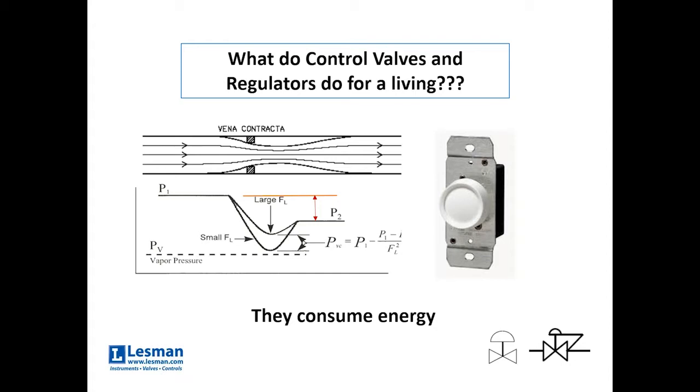What do control valves and regulators do for a living? They consume energy. And for those of you that can see the visual, I have the classic vena contracta shown where the energy in the pipe, the fluid is moving along. There's a restriction. In this case, it's a variable restriction because it's a control valve or a regulator that moves. But once it hits the restriction, it has to move faster.